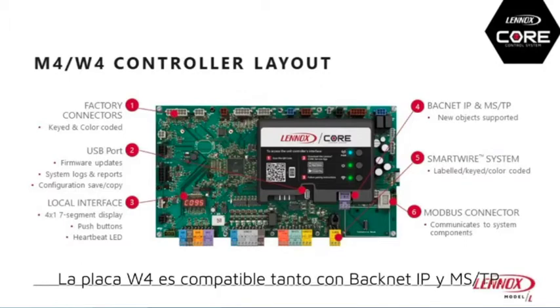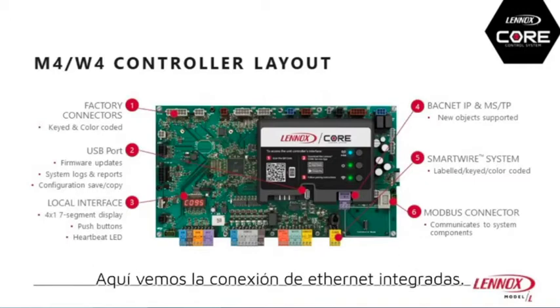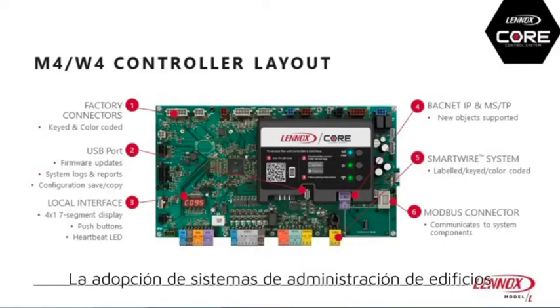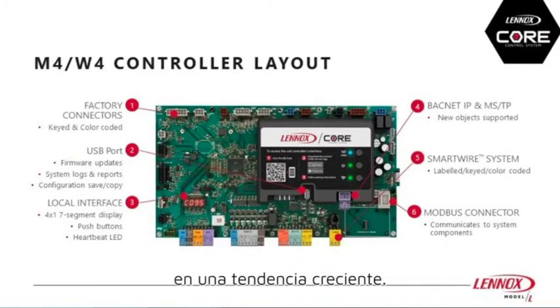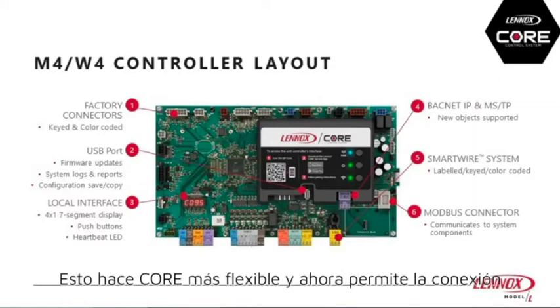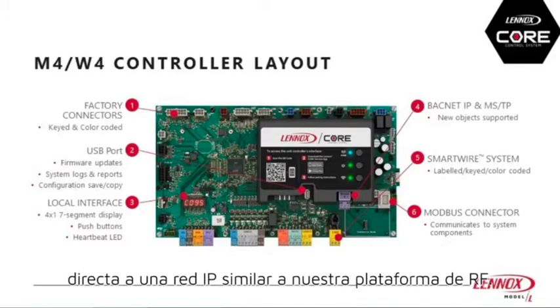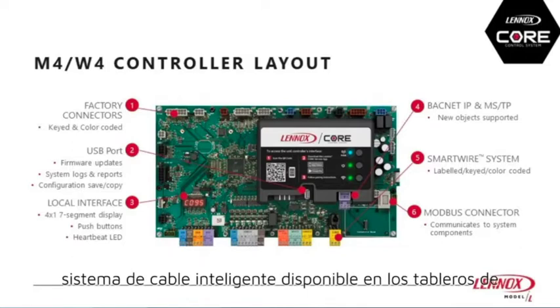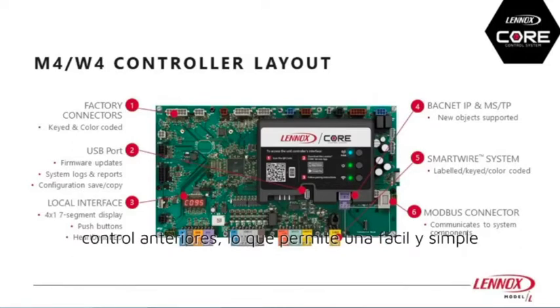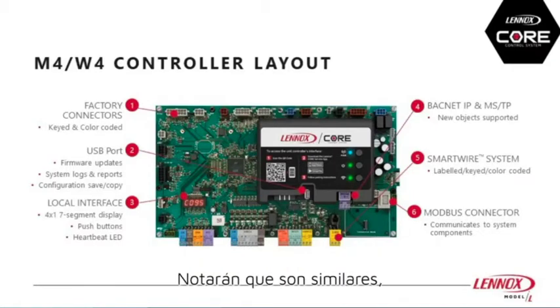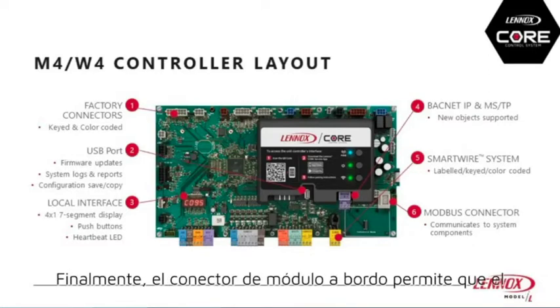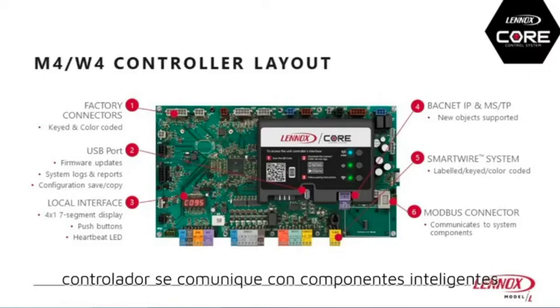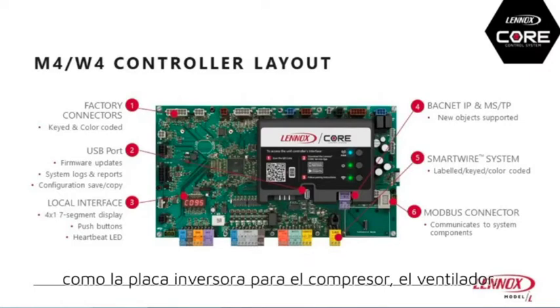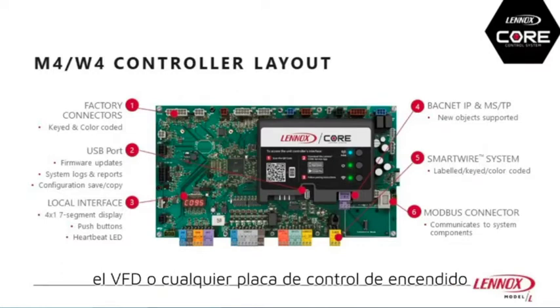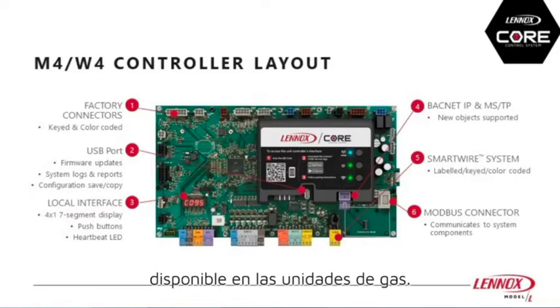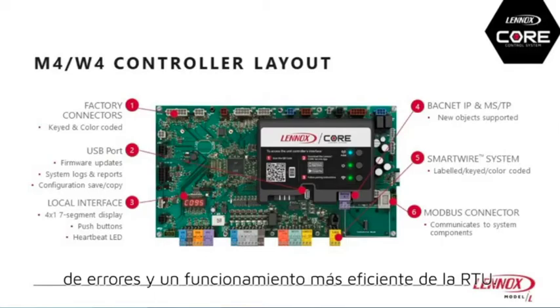The W4 board supports both BACnet IP and BACnet MSTP through the built-in Ethernet and screw terminal connectors that you see here. Adoption of building management systems for monitoring and saving energy is in a constant upward trend in our market today. This makes Core more flexible and now allows direct connect to IP networks similar to our VRF platform. The Core Unit Controller also features a smart wire system as available in prior control boards, which allows for easy and simple install of field components such as sensors. You'll notice that these are similar, but there are a few more new inputs. Finally, the Modbus connector on board allows the unit controller to talk to communicating RTU smart components, such as the inverter board for the compressor, the blower, or VFD, and any ignition control boards available on gas units. Smart components allow for clear error recognition and more efficient operation of the RTU.